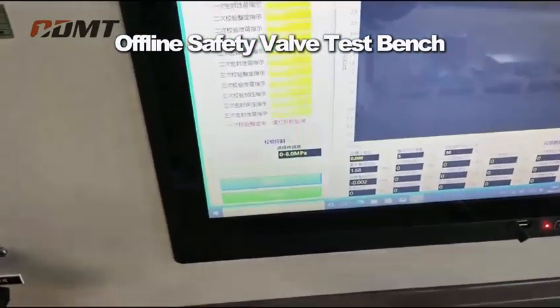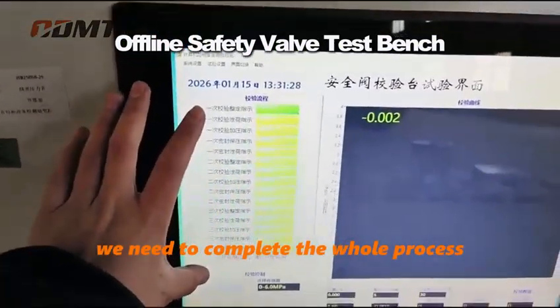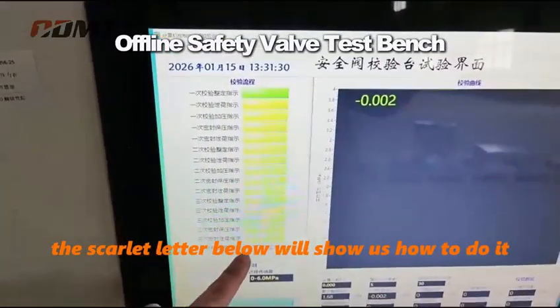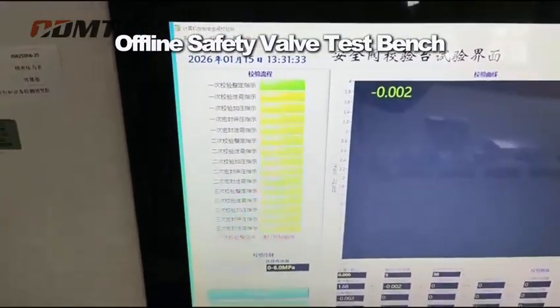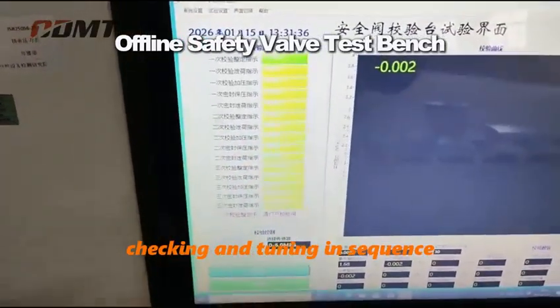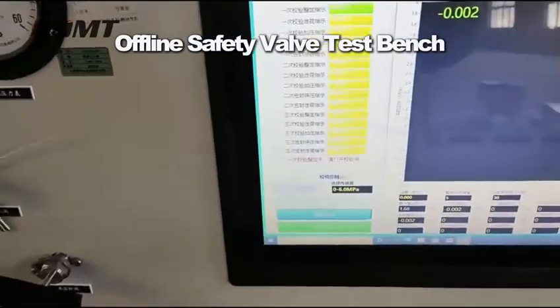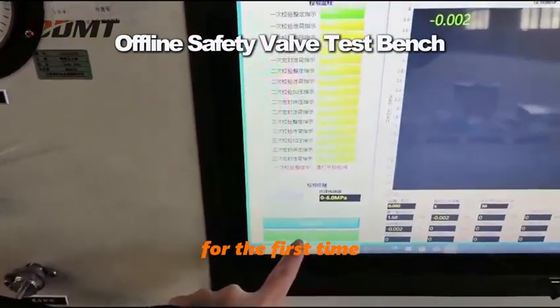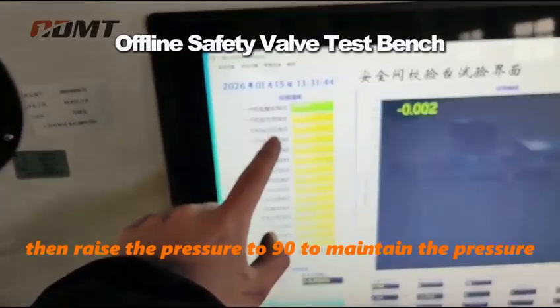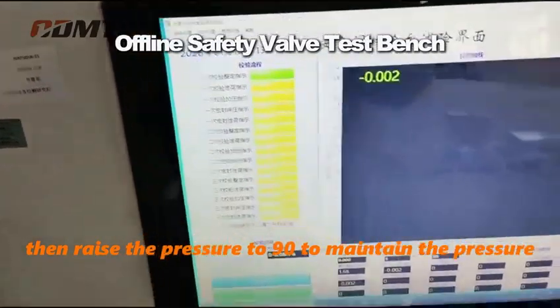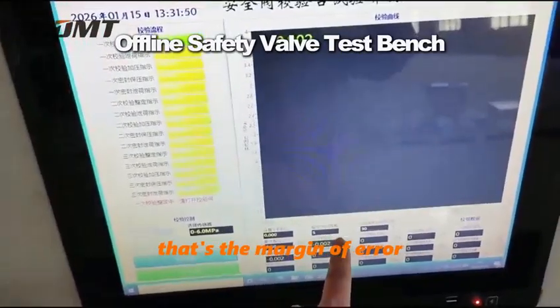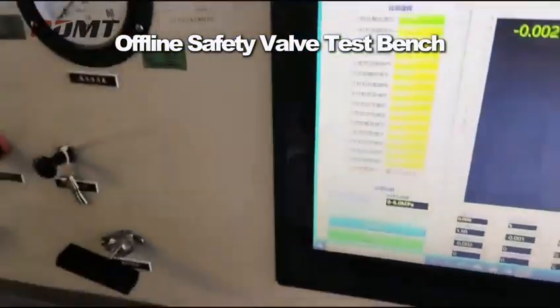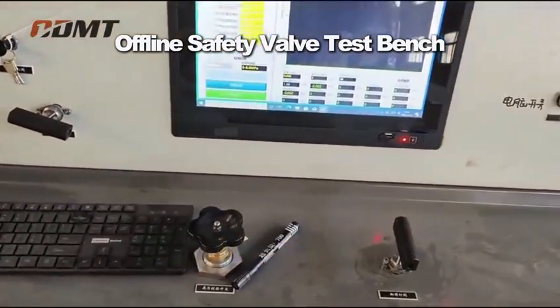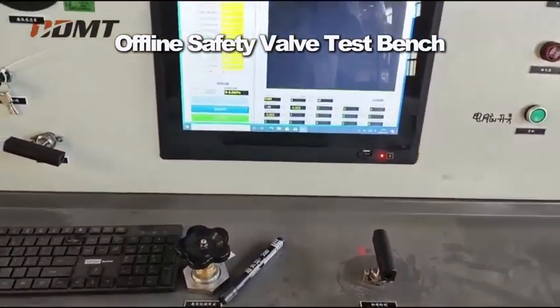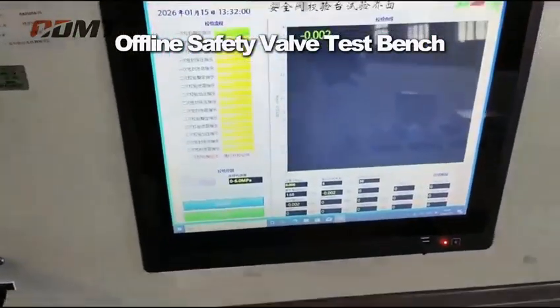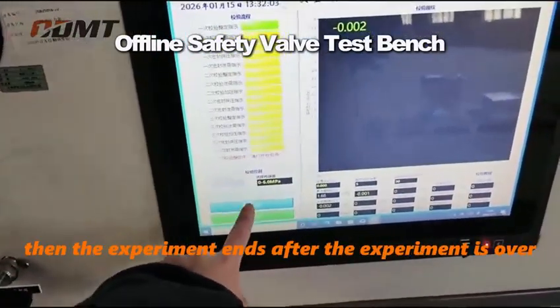After clicking Check Start Stop, we need to complete the whole process. The red letters below will show us how to do it and how much pressure to put, for example, checking and tuning in sequence. Please open the calibration valve. This lets us jump the safety valve for the first time. Then we need to decompress. Then raise the pressure to 90% to maintain the pressure. Here is the margin of error we allow for the jump, and the holding time set when holding pressure. After the whole operation is completed, the experiment ends.